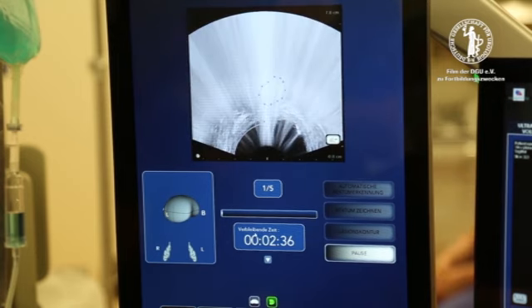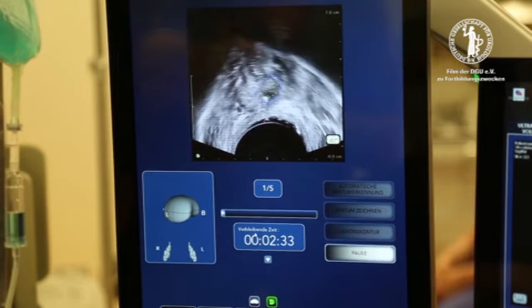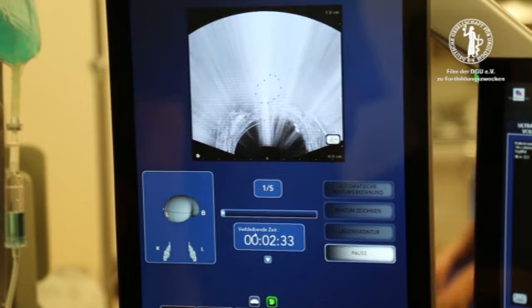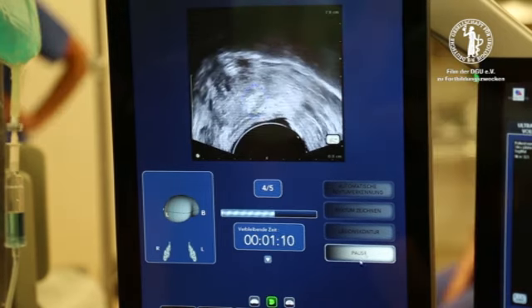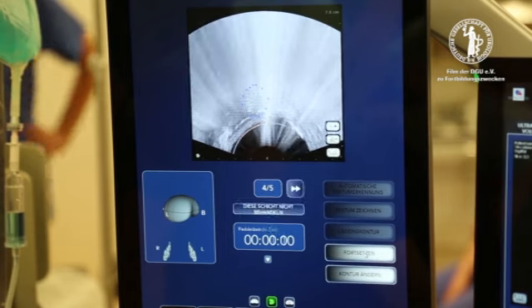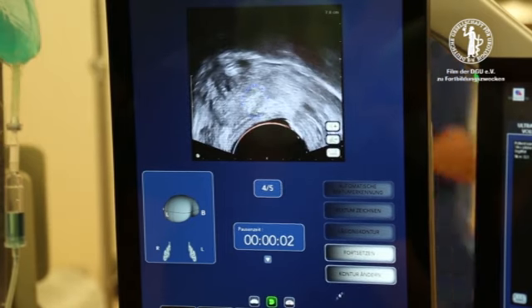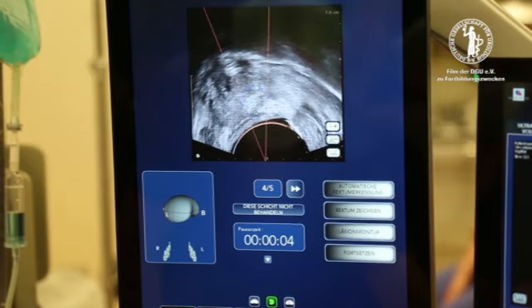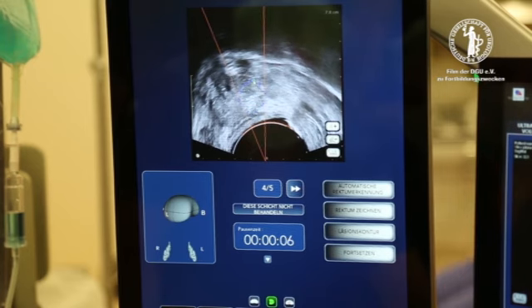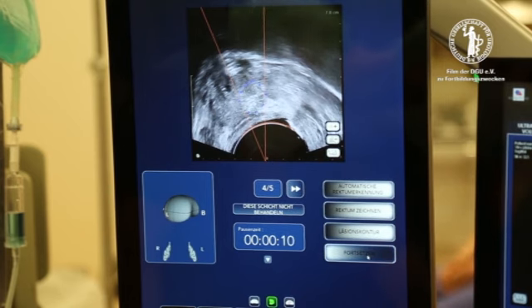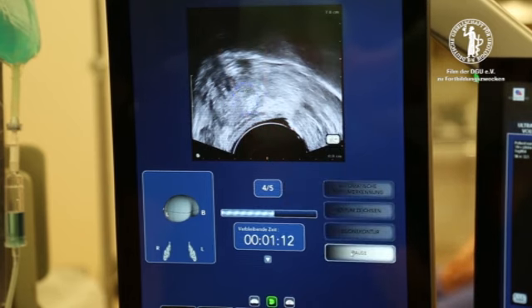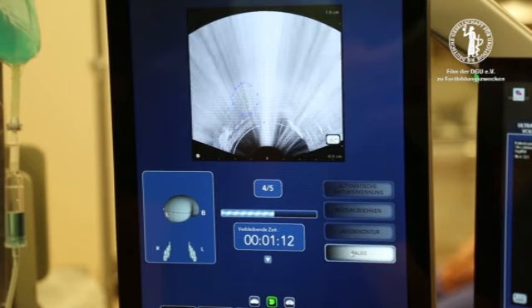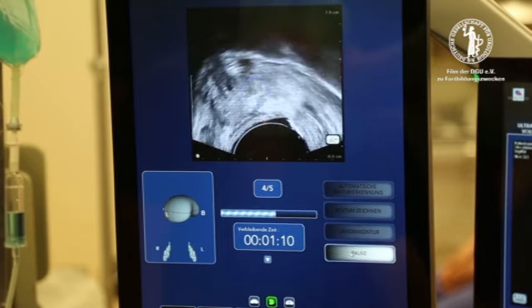Each subshot leads to a necrosis of an oval area of around 5 mm in size. Additional shots allow the lesions to be stacked. The movement of the probe relative to the rectal wall and the firing parameter are controlled by the software. The whole procedure needs close monitoring by the surgeon. Adjustment of the localization of shots is possible at any time during the procedure and is often necessary.